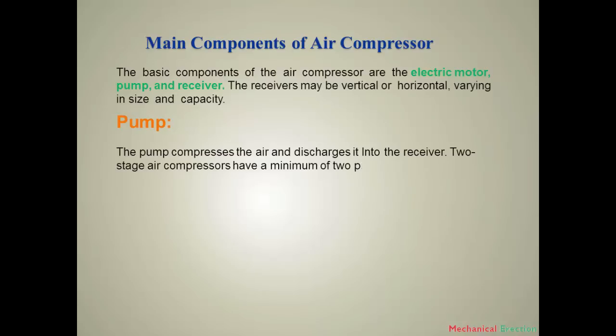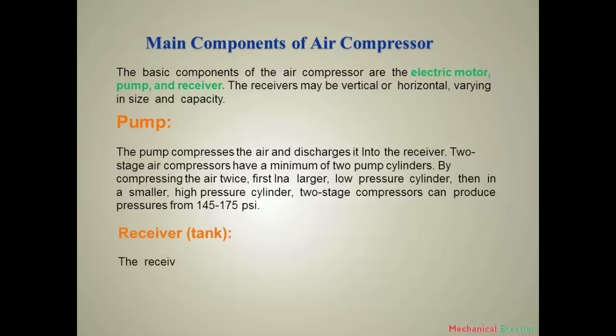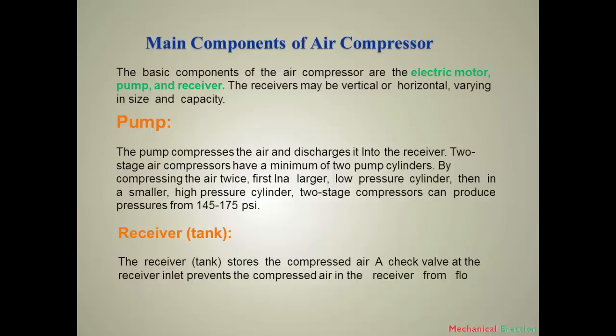The purpose of the pump is to compress the air and discharge it through a pipe into the receiver. Two-stage air compressors have a minimum of two pump cylinders, compressing the air twice — first in a larger low-pressure cylinder, then in a smaller high-pressure cylinder, producing low to medium pressure. The receiver is a tank that stores the compressed air. A check valve at the receiver inlet prevents compressed air from flowing back into the compressor pump — the valve must be operating, otherwise compressed air flows back into the pump.